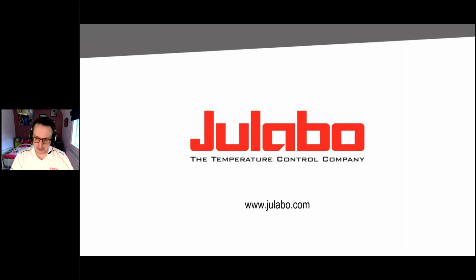The Presto series is a lot more sophisticated. It's not a chiller as such, it has a higher temperature range. A chiller, as we've talked about today, mainly replaces tap water, so it runs at a temperature of like 4 to 20, or 4 to 50 degrees. A Presto will cover a range typically of minus 50 to 200. So it's a different beast altogether.